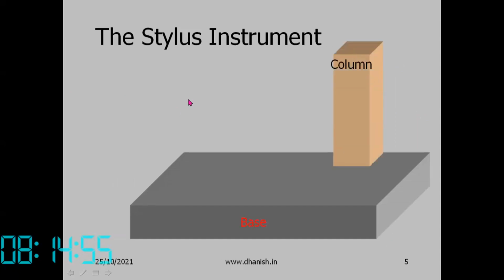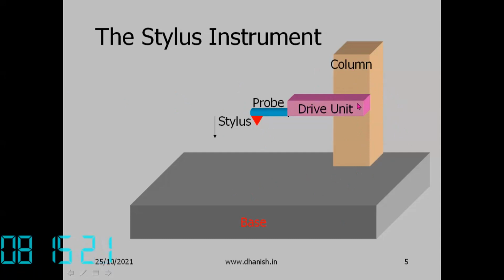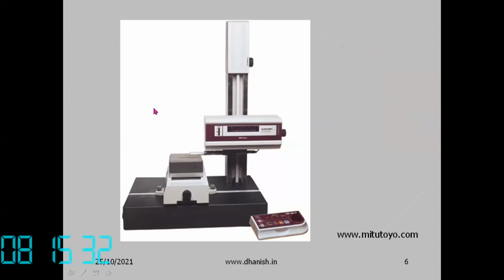So the stylus instrument. We have a column over which the drive unit is attached, and in the drive unit we have the probe. So the drive unit moves the probe forward or backward, and on the probe we have the stylus. So this is the basic structure. And of course, in portable units, this column base will not be there. You just have the drive unit attached to a sort of holder box which holds the drive unit. So this is one of the common types of instruments with base and column. Here we have the probe, and the stylus is here. This part is the detector.